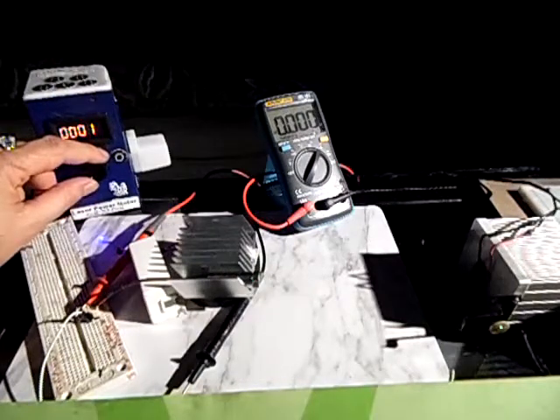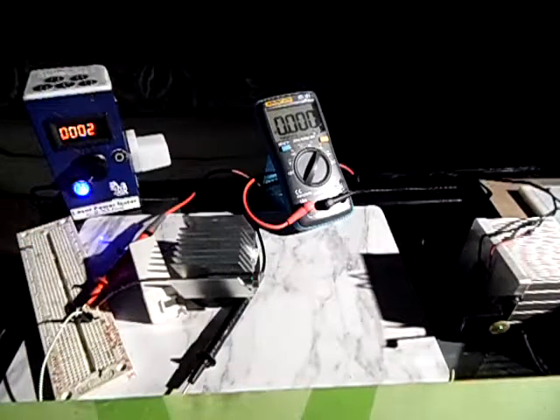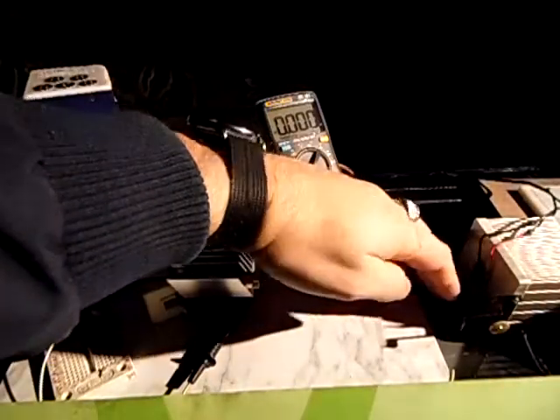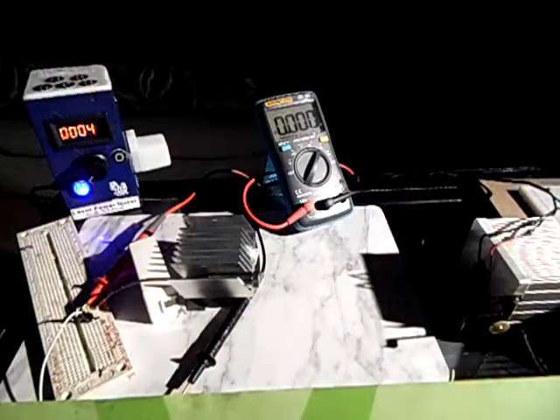What is important is to stabilize it, and that is very important. I see people testing using laser beam power meters and they literally put their hand near it. When that happens you're affecting the heat reading. You can never put your hand that close to it because you're not measuring the laser — you're just measuring your own body heat being transferred onto the sensor. If you touch it, you just never, never put your hand anywhere near it, otherwise your measurements won't be right.